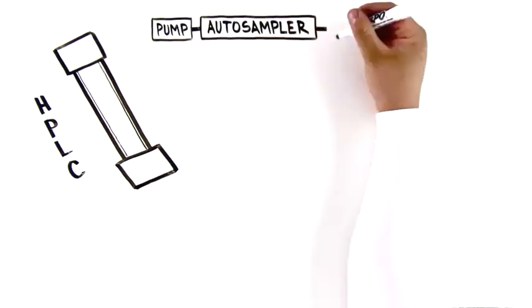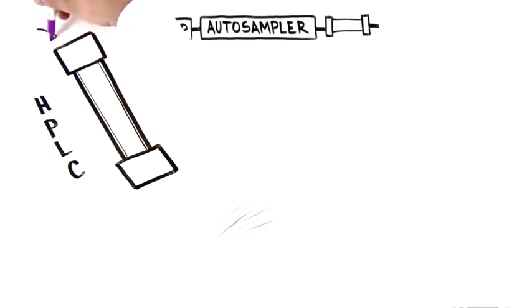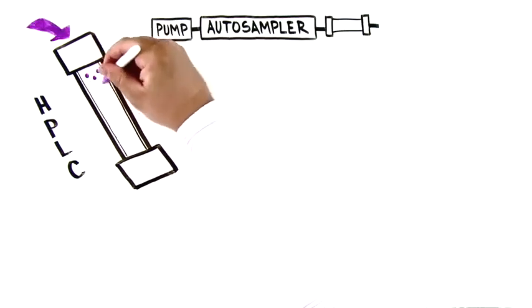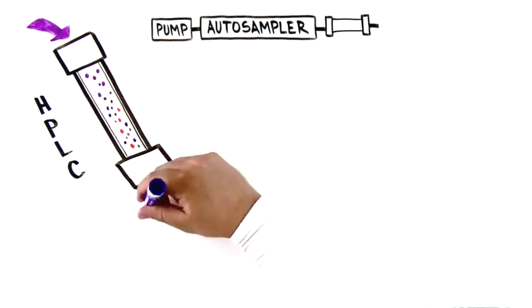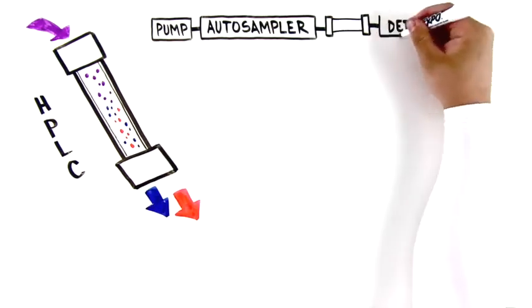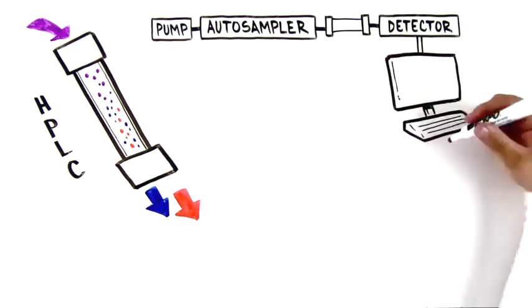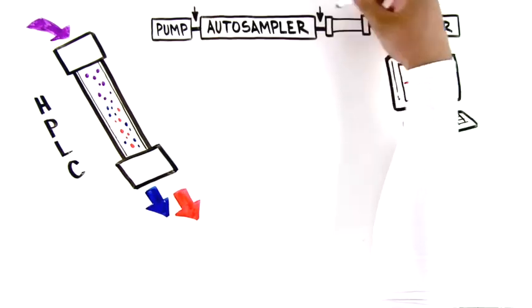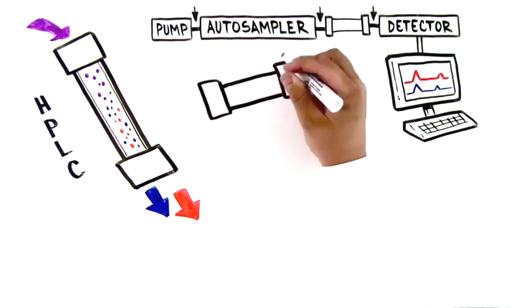After the pump, the eluent passes first the autosampler where the samples are injected on the column. The sample is then separated in the column. Finally, the detector measures the compounds. All these different modules of an LC system need to be fluidically connected by some tubing.